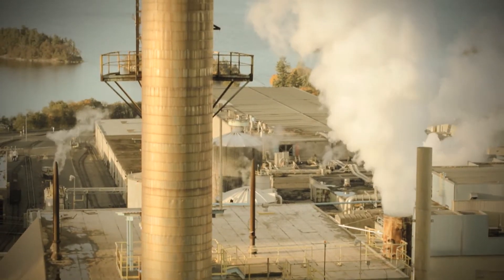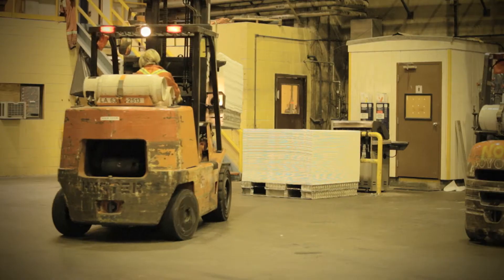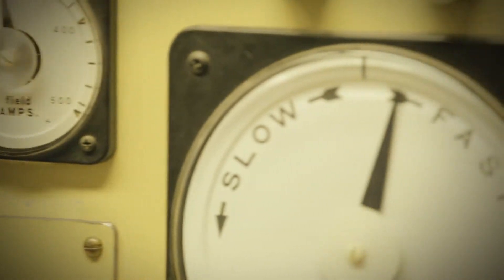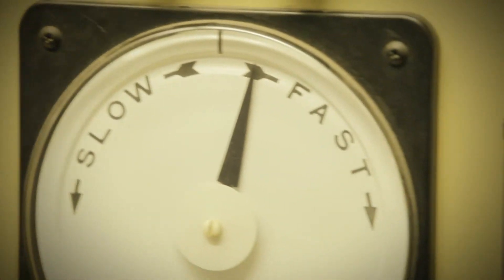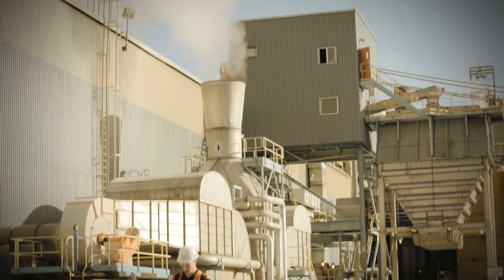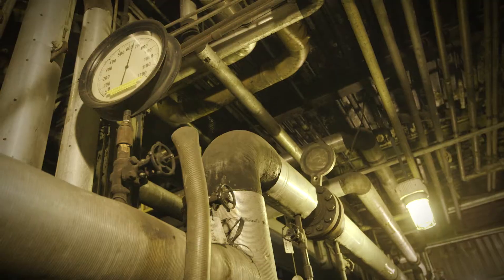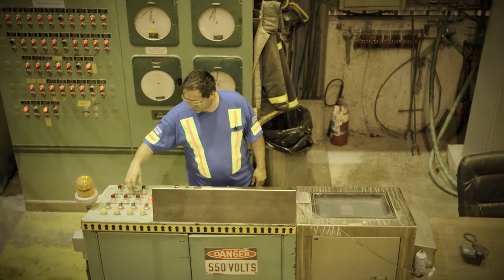Our primary goal is to make steam, and we make steam for the pulp and paper process. My job is to maintain water level in the boiler. If the water level goes too high, we can put water down the steam line. If it goes too low, we can overheat the metal tubing and cause metal fatigue and failure. So we have to monitor the environmental aspect of the boiler, its efficiency, and the day-to-day mechanical parts we maintain on it.